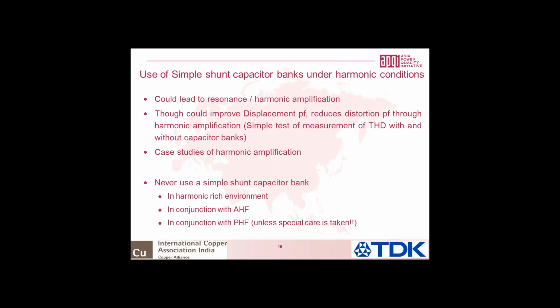Now, it's a very simple case. I don't want to get into complicated mathematics, but we know that when you connect a simple capacitor bank, this could lead to resonance or harmonic amplification. This could be either a series resonance or a parallel resonance. I've seen both. Though one could improve the displacement power factor by injecting a larger capacity VAR, this could reduce the distortion power factor, which in turn would reduce the true power factor.